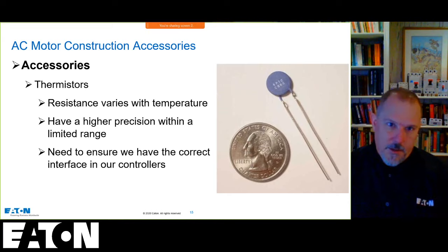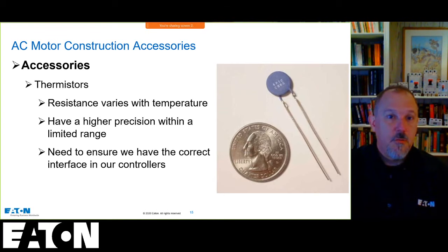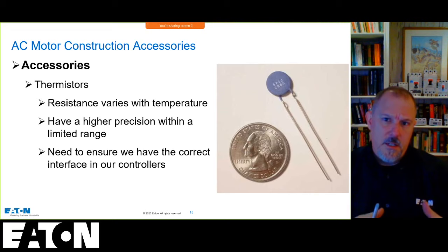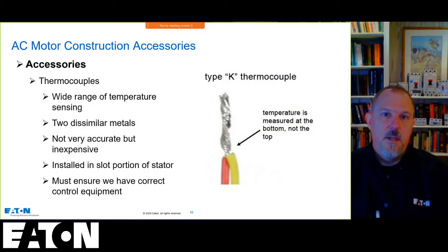Thermistors, another way to detect the temperature, higher precision with limited range. Again, we'll use these types of devices for different types of motors and different types of applications, and more critical motors, watching the temperature rise. Temperature will rise in a motor for a lot of different reasons. It might not just be because of imbalance or a problem inside. It could be because of wear and tear on bearings, etc. There's a lot of different reasons for the temperature of that motor to rise. And using these types of accessories can help detect that failure or that there is a problem.